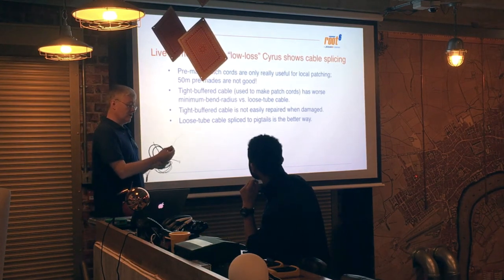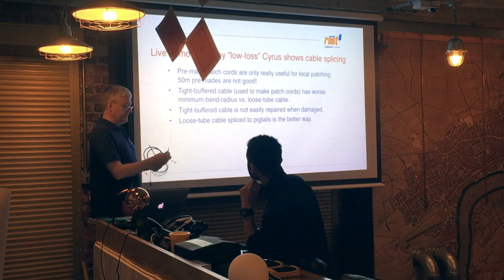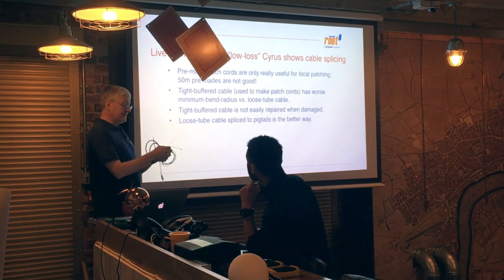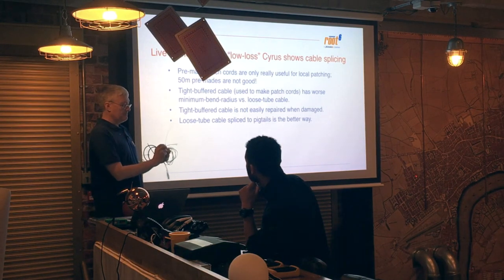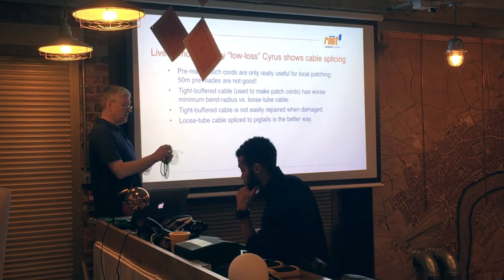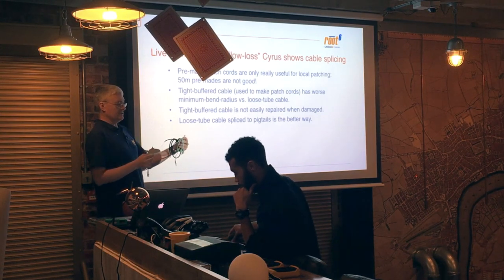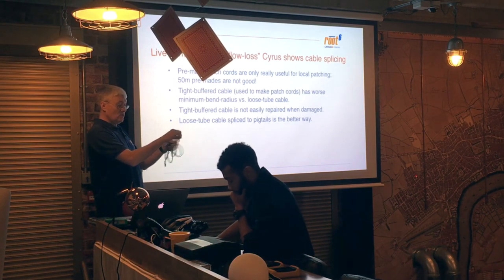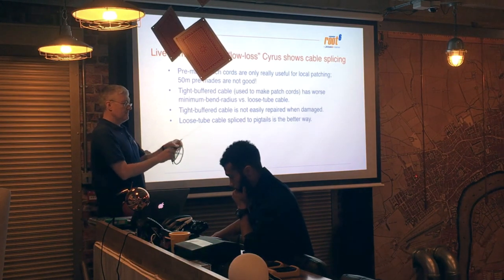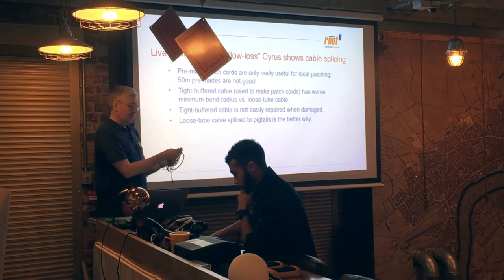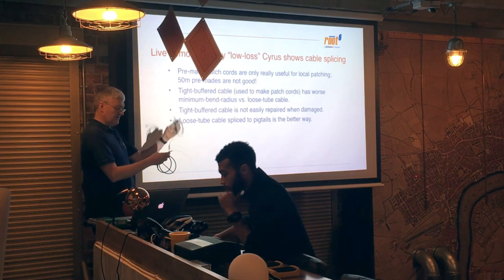For running through ducts and under floors, we recommend a loose tube cable. In this type, the actual glass fibres aren't adhered to anything — they sit in a plastic pipe full of mineral oil. One benefit is a much better minimum bend radius: with a tight-buffered cable, bending it sharply causes massive losses and risks damage. With loose tube, the fibres are able to slip and slide over each other within the oil bath, giving a much better minimum bend radius specification.